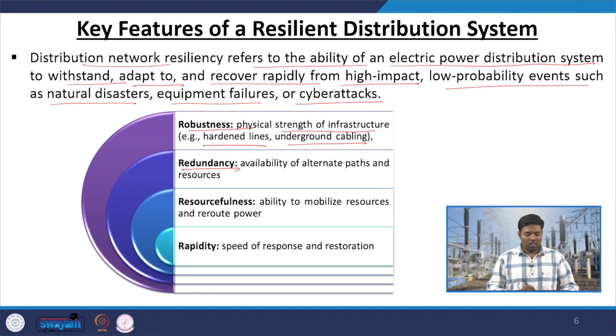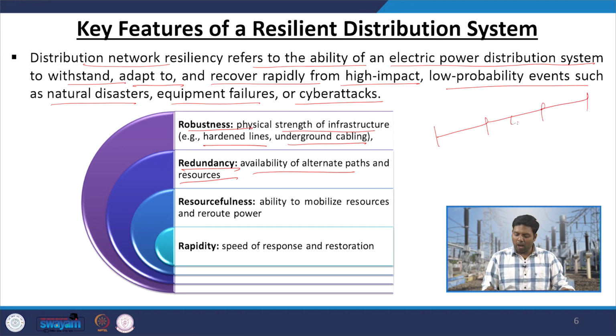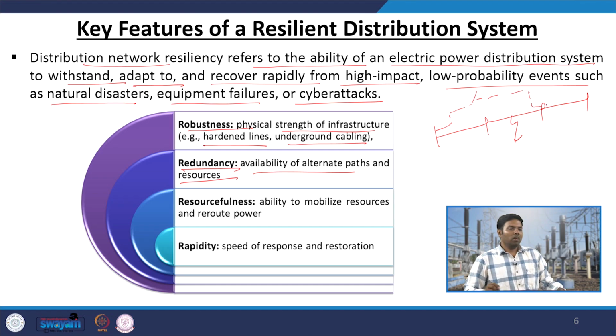Second is redundancy, the availability of alternate paths and resources. If you have a radial network and something happens to it, you must have an alternative switching path to send power to the underlying network by closing that switch. So you have a redundant connection for an alternative path, rerouting power to the disrupted customers.